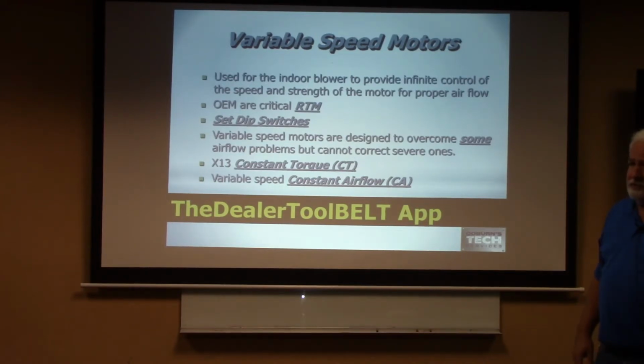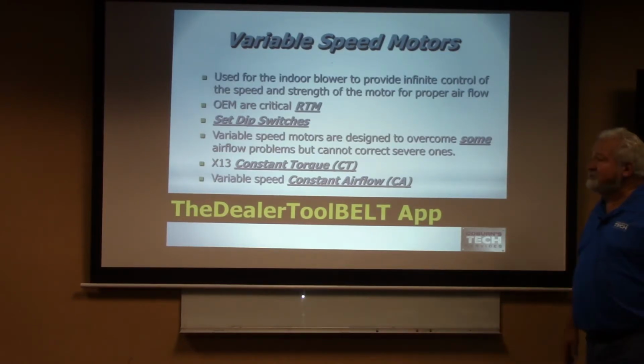Set the dip switches. They don't come from the factory with the dip switches set. How many calls do you get, Jody, every week on, well, I left it that way because that's how it came from the factory? Yeah? Lot, absolutely. Variable speed motors are designed to overcome some airflow problems, but can't correct severe problems.